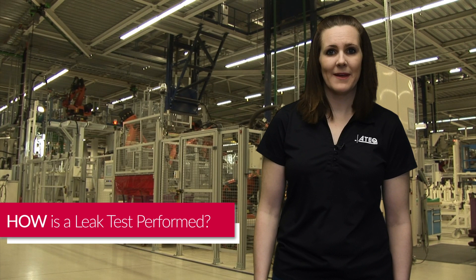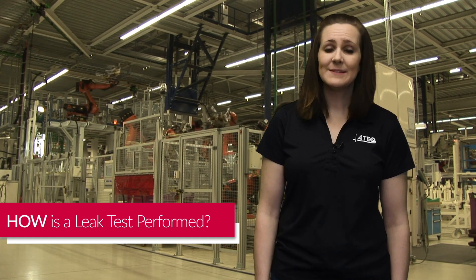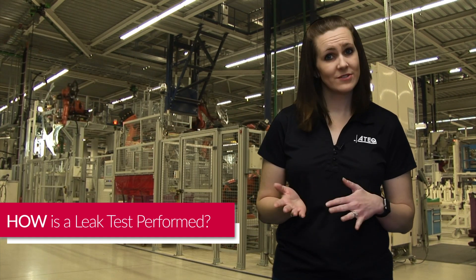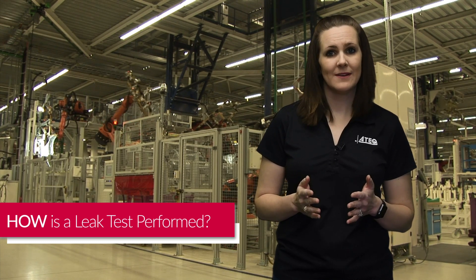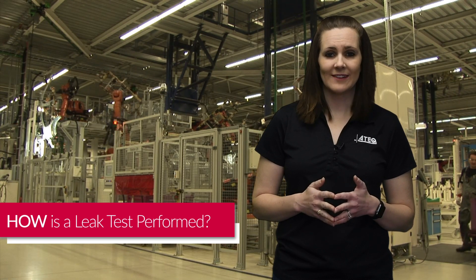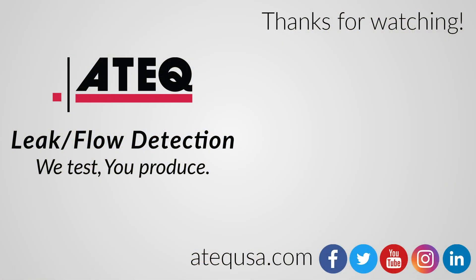ATEQ's primary method of testing is pressure decay air leak testing. This means that the instrument injects the part with compressed air, measures the pressure, waits, then measures the pressure again to see how much the pressure dropped. If the measured leak rate is less than the designated reject limit, the part passes the test. Thanks for joining me in today's informational leak testing session. We'll see you next time.